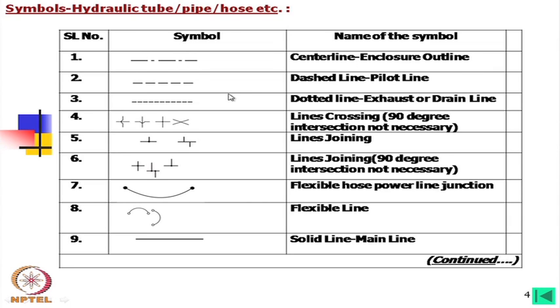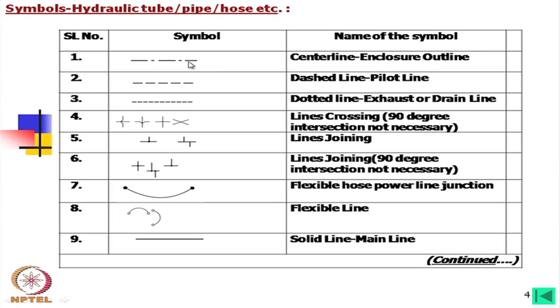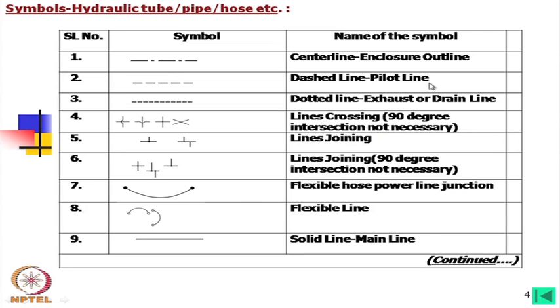The enclosure outline means that sometimes we have a manifold — a manifold consists of a few valves together. The symbols for all components, like a pressure relief valve and direction valves, are drawn separately and then enclosed by this line, indicating it might be a manifold. The dashed line means this is usually the pilot line.